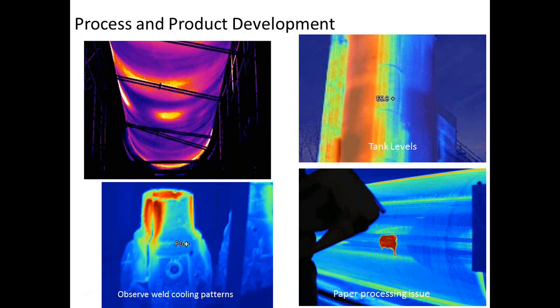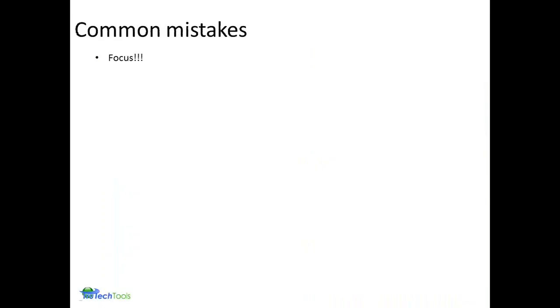Common mistakes in thermography, and focus is probably one of the most common. It's something that has to be mastered when you start to use infrared. One thing that you can't fix with an image - because of the digital technology, most information captured with an infrared camera can be modified in software, but focus can't be changed.